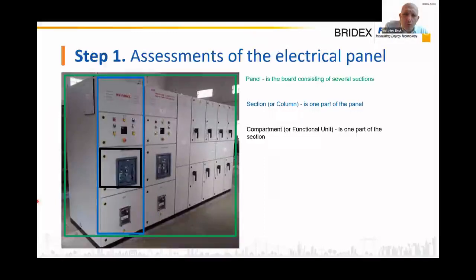Just to bounce back, there's a misinterpretation on the video we showed. We tripped the breaker to demonstrate the dry contact output, but in reality this system is meant for prevention. We detect and alarm at 100 degrees, and there's no fire at that point - the fire starts much later. The point is to enable prevention, to cure problems earlier than when fire starts.